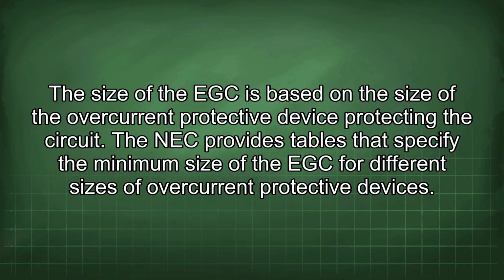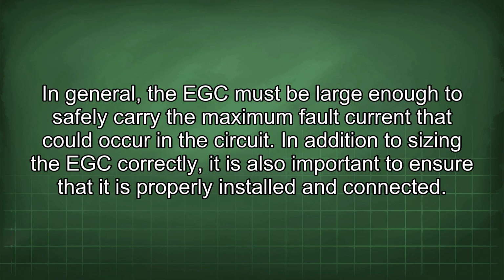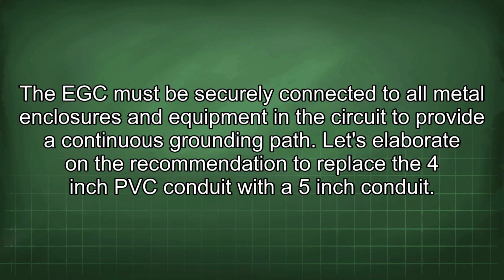The NEC provides tables that specify the minimum size of the EGC for different sizes of overcurrent protective devices. In general, the EGC must be large enough to safely carry the maximum fault current that could occur in the circuit. In addition to sizing the EGC correctly, it is also important to ensure that it is properly installed and connected. The EGC must be securely connected to all metal enclosures and equipment in the circuit to provide a continuous grounding path.